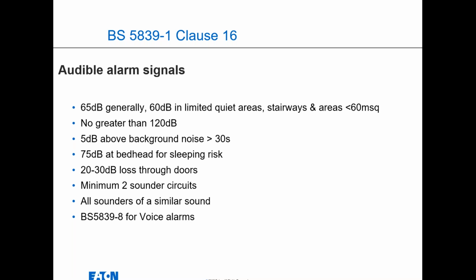It shouldn't exceed 120 decibels, which most manufacturers' sounders don't, unless you're into industrial stuff. And then you should be 5 dB above any background noise. Again, how do we know what the background noise level is? But you've got some information in the back of 5839 that gives you some standard background noise levels. If you're in a hotel or any sleeping risk accommodation, you should be achieving 75 decibels at the bed head, so where you sleep.